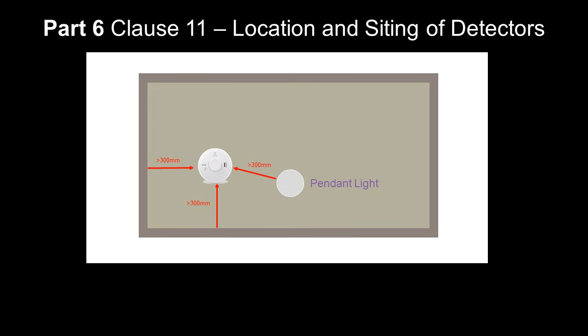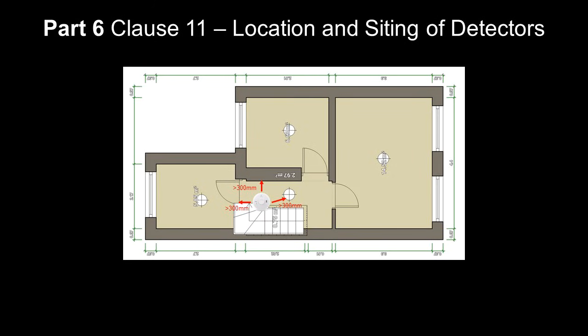In some instances, this is a bit of a pain, because we might have an awkward shape, and we know the lighting layout takes precedence over the fire alarm detectors. We know this. People don't like these ugly detectors on their ceilings. So you have to be a little bit sensible about it. There are instances where your detector might look a little bit out of line with your lighting layout, because your pendant, for example, might be closer than 300mm to the wall. So we have to be a little bit sensible here, but again, we have to make sure that whatever we're installing is going to detect a fire.